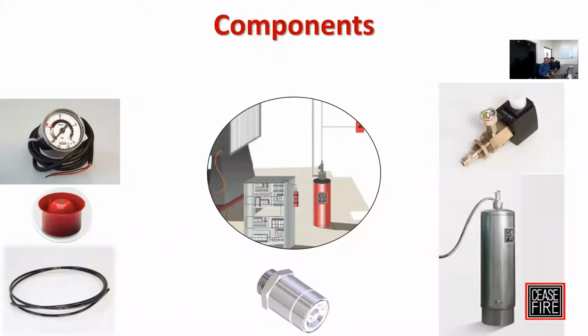These are the major components you can see. At your left, I will start with the pressure switch. Through this switch, you can give a trigger to any third-party system, your building management system, or your fire alarm system. So in case the system is activated, you would also know that a fire has happened inside the generator. You can add a hooter. The tube works as the detection mechanism. I'm again reiterating that this system is purely mechanical. The pressure switch and the hooters are only for the output, and they work on electrical power, whereas the system is purely mechanical, and in case of fire, it will be actuated.